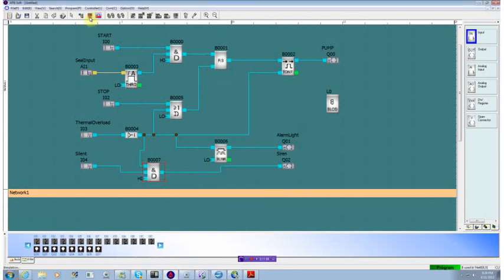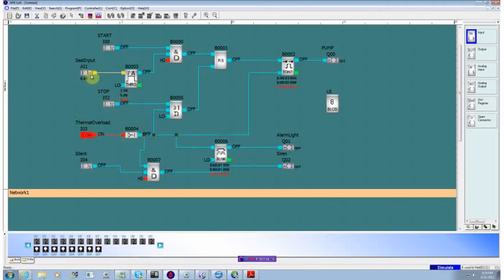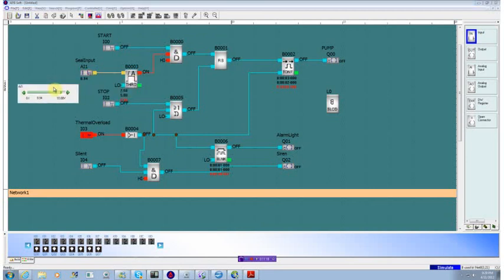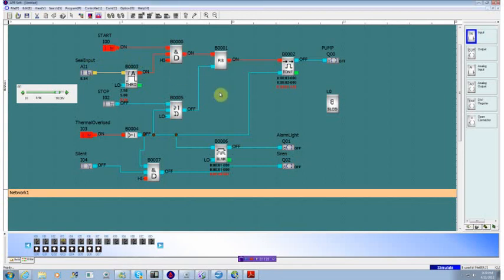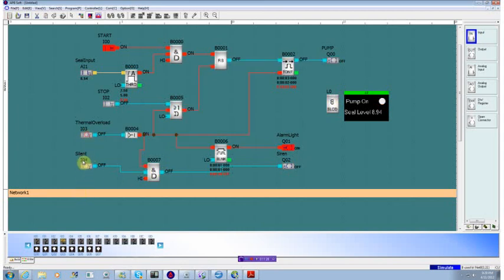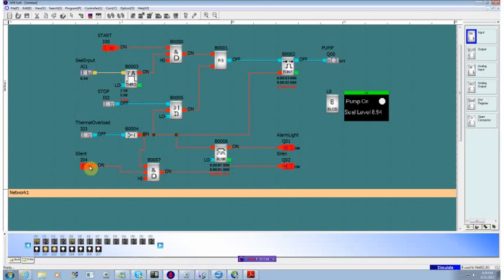So now when we run our application, the thermal overload should be always closed. The threshold should be up around eight or nine. We start our pump, pump starts up. We see that we have our display running. The thermal overload trips. The alarm light starts to blink on and off once a second. The siren though right now is off because this is open. If we turn that on, the siren would be running. So that completes our application.